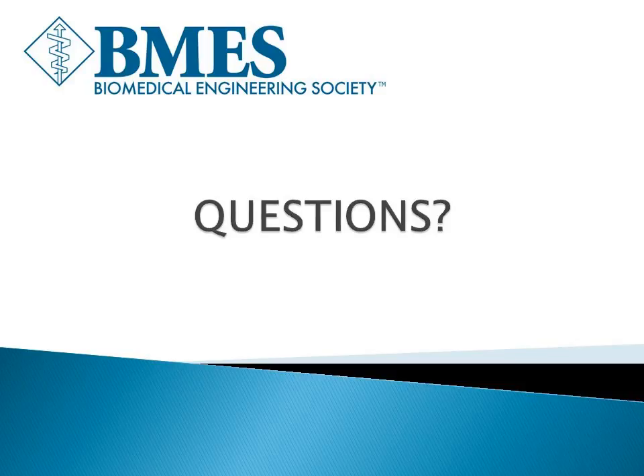Medical device development tool is a recent program. It's been generally the past 2 or 3 years. It's a recent program by the FDA, and the idea is really to qualify tools the medical device sponsor can use in the development and evaluation of medical devices. And the qualification means that the FDA has evaluated the tool and concurs with available supporting evidence that the tool really produces scientifically plausible measurements and works as intended for a given context of use.